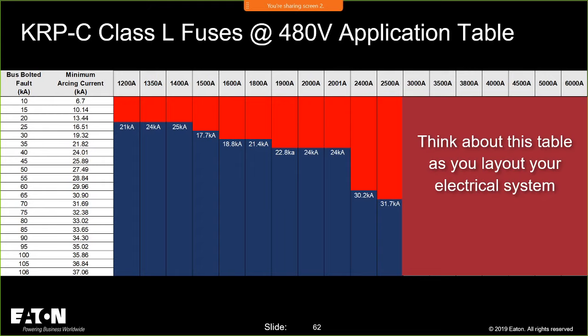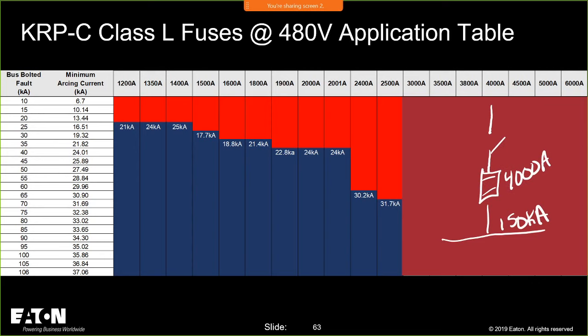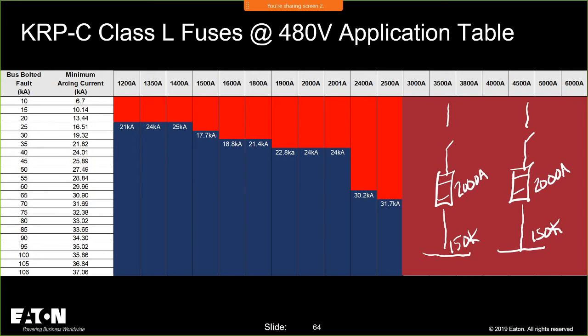I have a design that has, say, a 4,000 amp fuse, and I have 150,000 amps of available fault current. What do I do? Well, you're either going to put an arc reduction technology on that, or you could split that 4,000 into two 2,000 amp fuses. And if you do two 2,000 amp fuses, I know, because the 2,000 amp fuse is right here, that all I need is 24,000 amps of bolted fault current.